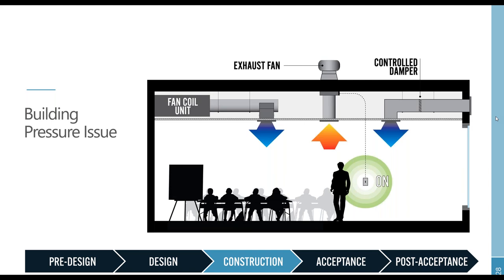What we discovered was, in their attempt to try to fix the initial issue, they had utilized a sheet metal screw to just force the damper to be automatically opened, and it would be open 100% of the time. What this did was it allowed the air to come into the space and then immediately go out through the damper, meaning we were wasting energy by cooling down a space that was then just releasing air right back outside. So we told them to make this change.